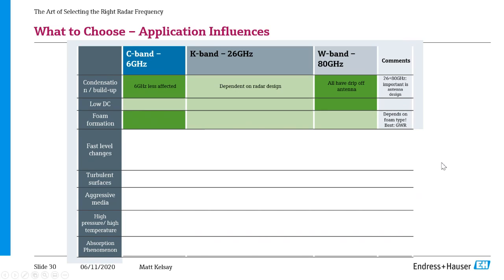Foam is a fairly difficult topic, as unfortunately all foam type applications are different. What I've put on this chart is assuming that you want to ignore the foam and measure the liquid level underneath. In that case, similar to condensation, your low frequency is going to be better there because that lower frequency will penetrate through that foam and get a bigger signal reflection off the surface of the product. However, if you were actually wanting to measure the top layer of the foam, you'd be better off to go the opposite way and use a high frequency device.